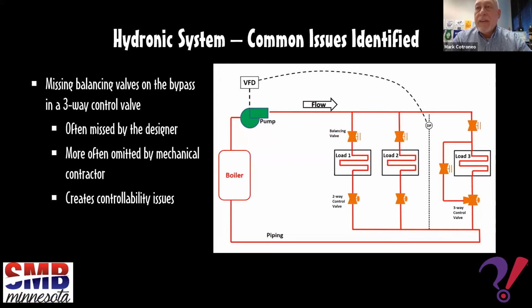I think if on the TAB process we have temperature control, say at something like 75% completed, then we can start, similarly, like I know you do, Rebecca, when the TAB process is about 75 to 80% complete, then you can start your process. You don't have to wait till the very end, but you do have to have so much of the volumes set and working so that the controls can work, or so that the system works correctly.